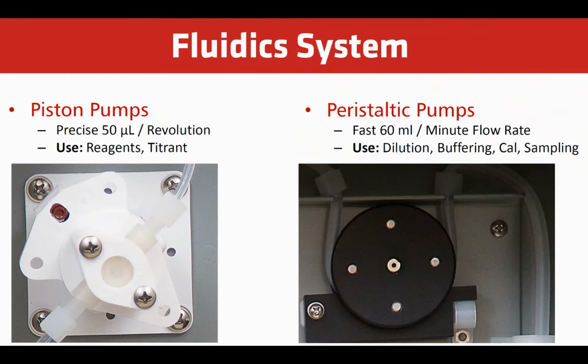So we use what's called piston pumps, and these are for very low level. Each revolution will inject 50 microliters or less of reagents. And these are typically used for reagents where we only use very low milliliter quantities, or for a titrant, because when you're doing a titration, it's very, very critical to know the exact amount of titrant delivered to calculate an endpoint.